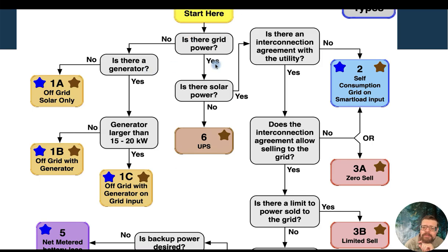If we do have grid power, then we immediately get to the UPS type systems. If we're not doing any solar, but we do have grid, then all we're doing is backup power, and we have the UPS setup. This one can be changed later to setups that do have solar. If we do have solar power and grid, then the big question is: is there an interconnection agreement with the utility? If there is no interconnection agreement with the utility company, then we're not allowed to operate in parallel with the grid, and that immediately puts us over in system type 2. We'll go through more details of all these system types in a minute.